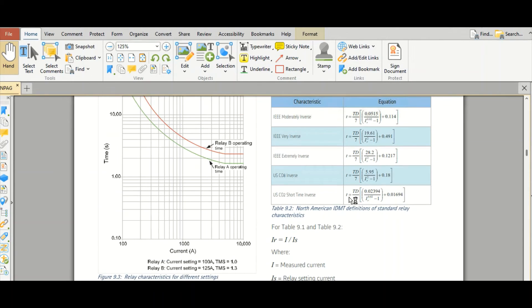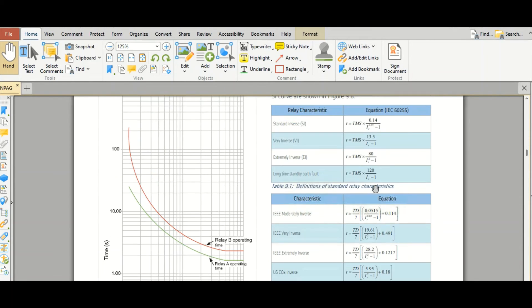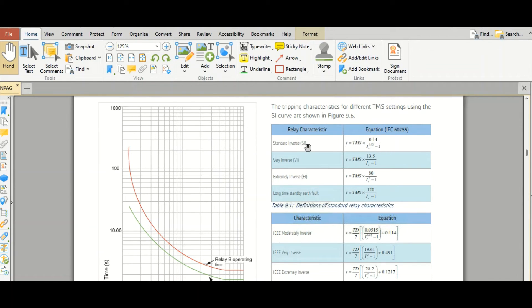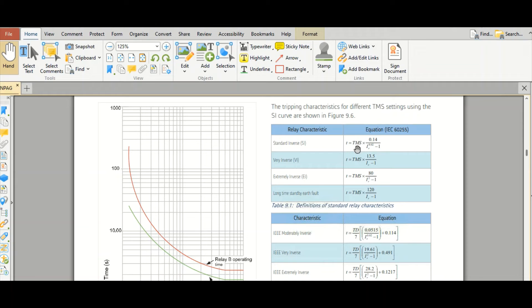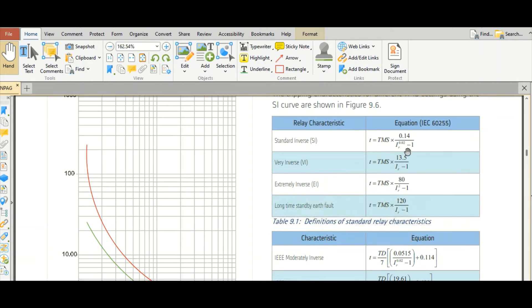Yeah, already I have seen this is IEEE formula. This is IEEE formula and this is IEC. As per IEC equation, IEC 60255, standard inverse curve will follow this formula: small t equals to TMS, time multiplier setting, multiplied by 0.14 divided by IR to the power 0.02 minus 1.